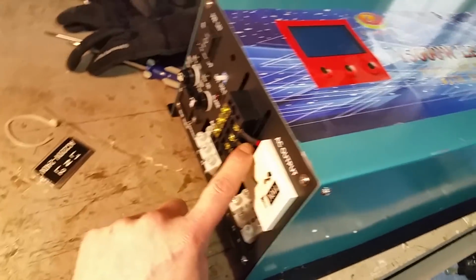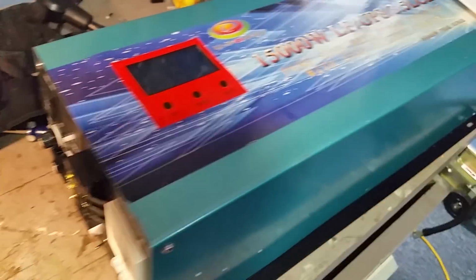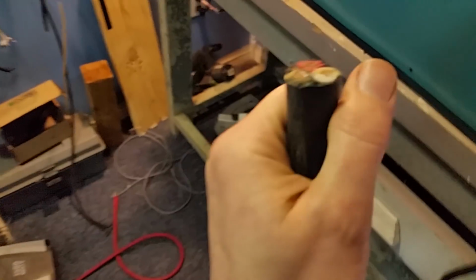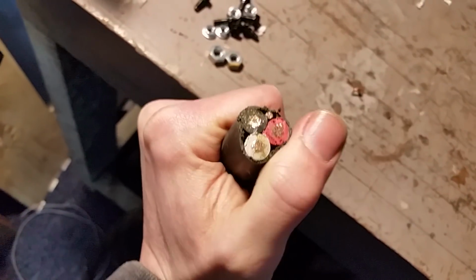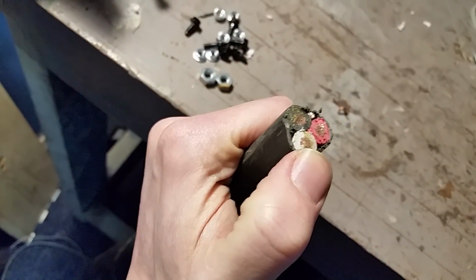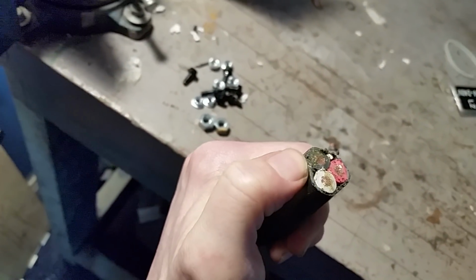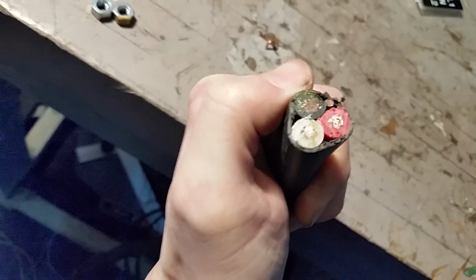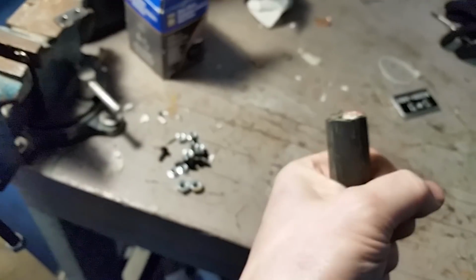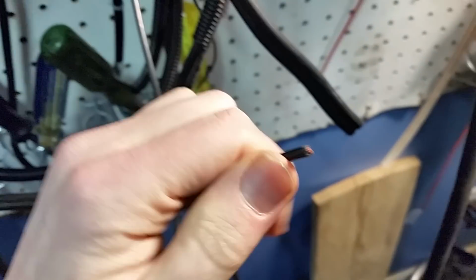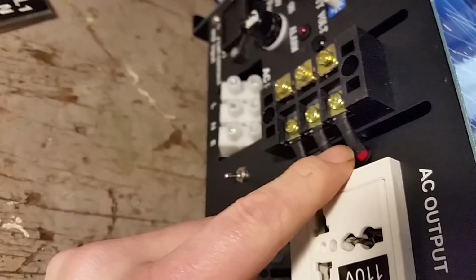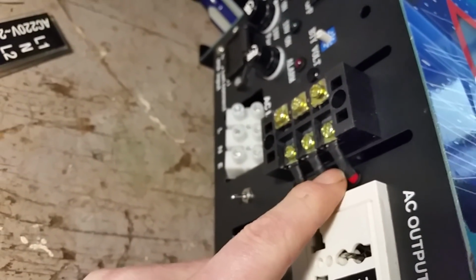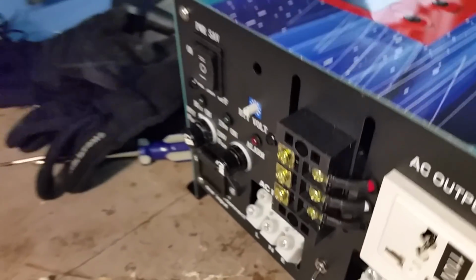So, 20 amp fuse, thin wires - let me show you. If it was really rated for 69 amps, this is the kind of wire you'd actually need. This is burial cable, meant for a hot tub, which goes on a 50 amp circuit breaker. That's the thickness of the wire, never mind the insulation. Because this burial cable is meant to go underground where it's wet, the thickness of that copper is meant for a 50 amp circuit breaker. This other one is meant for a 20 amp circuit breaker - nowhere near 50 amps, never mind 69 amps. That's just ludicrous.